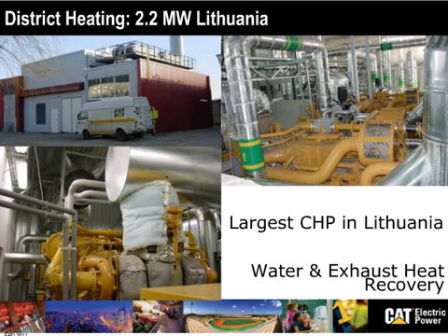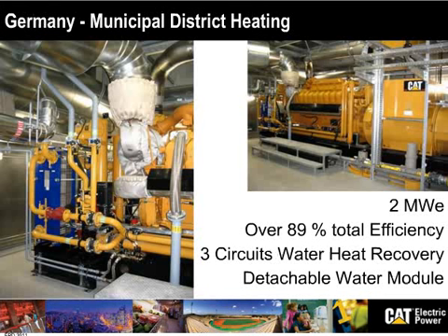This one is from Germany. And in Germany, we have numerous applications of that nature. Actually, we have 10 copies of this one at 10 different cities. In that particular case, what is very nice in this application for district heating as well is the very high efficiency, close to 90%. The 3-circuit heat recovery and a detachable module you can see in the front with the heat exchanger here in blue. This is the heat exchanger module from jacket water, aftercooler, and oil circuits of the genset.